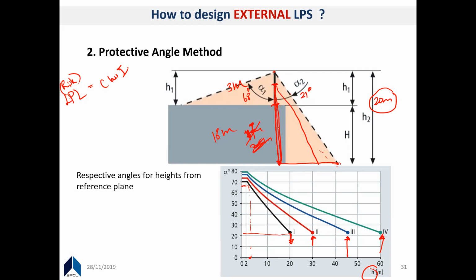If you are exceeding these values, the curves are not defined, so you cannot create a protection angle cone using these graphs. For example, if you have an 18 meter building, you cannot have a 3 meter arrestor, because then overall it will be like 21 meters total height, and then you cannot define a protection angle for this application. So you will have to make it shorter and check it out. If you make it shorter, the problem is the angle will be like this, and you will see you are coming nearer and nearer to this edge. If it goes beyond this, if your arrestor becomes shorter and shorter, then if you try to draw the protection angle, you can see a particular area is not protected. That's what happens when you design this.